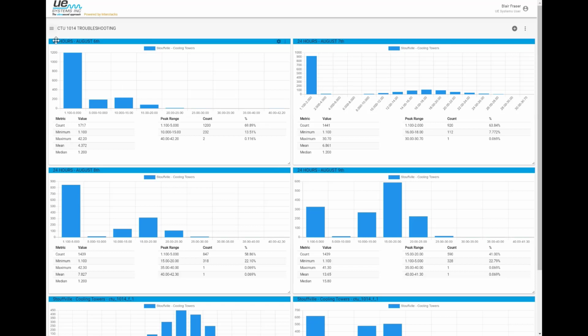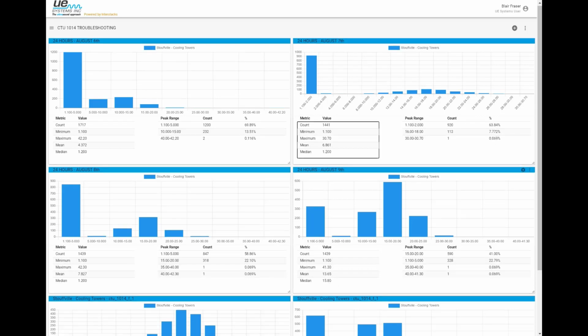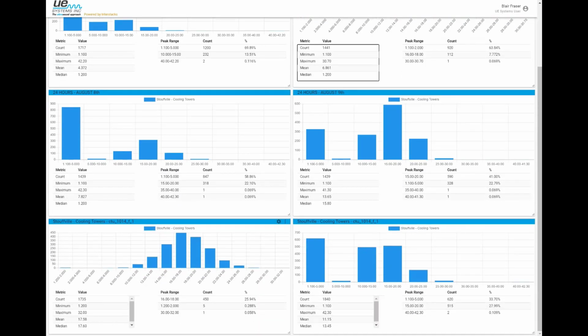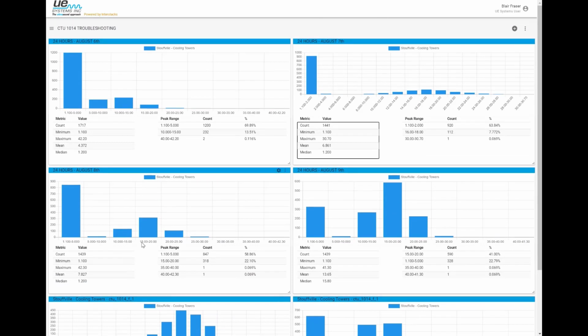Here I'm using a 24-hour trend of that specific bearing that had the lubrication issue. What's interesting is, day after day, starting on August 6th, I can see my mean value of decibels was 4.3. The next day it was 6.8. The next day it was 7.8. The next day it was 13, almost 14. Then it went up to 17. So this is an indication of how I can further troubleshoot this data.